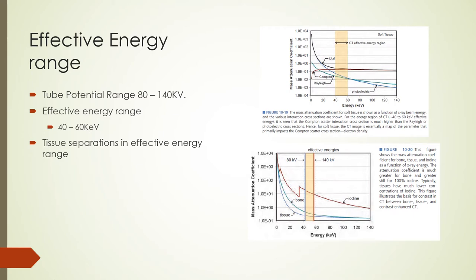The mass attenuation coefficients of Compton and photoelectric interactions are well separated in this region for soft tissues. The lower curve shows the mass attenuation coefficients of various tissues, showing the separation between iodine, bone, and soft tissues at the effective energy range. Some vendors offer 90 to 130 kV tube potential, so effective energy will be slightly different. The differences in mass and linear attenuation coefficients of tissues is what makes CT imaging possible and is unique to the CT modality.